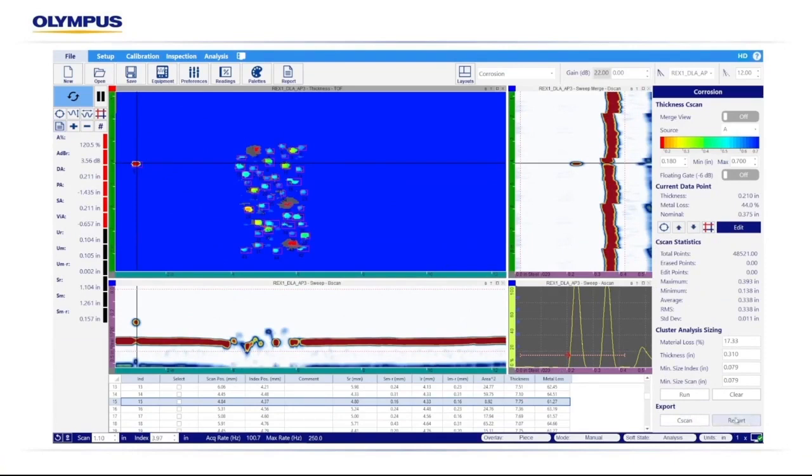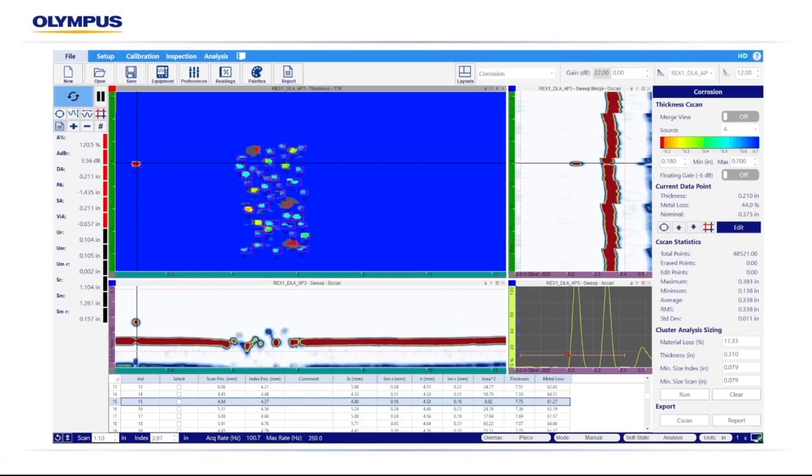Once we're happy with our results and we've went through our data in our indication table and verified those are relevant indications, we can go to the bottom right-hand side of that corrosion manager where we can either export the C-scan, which will save that C-scan as a CSV file with the color palette all intact, and then we can import that into an asset management software, or we can go ahead and generate our report and complete that inspection.